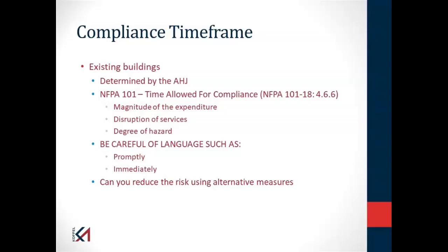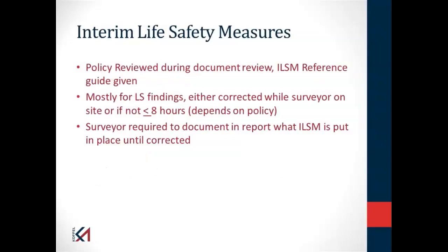But the other question you should be asking yourself is, during this period of noncompliance, are there things that we can do that will reduce the risk associated with the fact that we're not in full compliance with the code? So I'm going to use a concept that's in the healthcare community, and this deals with one of the accrediting organizations. They have this concept of interim life safety measures. The acronym is ILSM. And basically they say that if a situation cannot be corrected while one of their surveyors is on site, the facility needs to evaluate the need for an interim life safety measure.